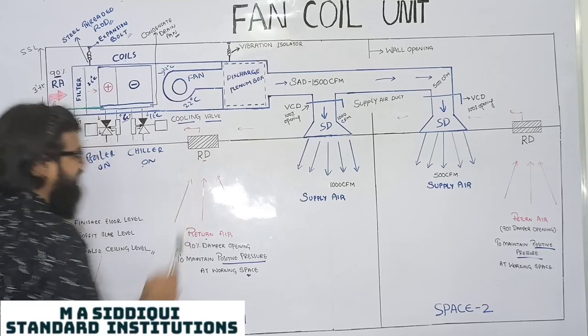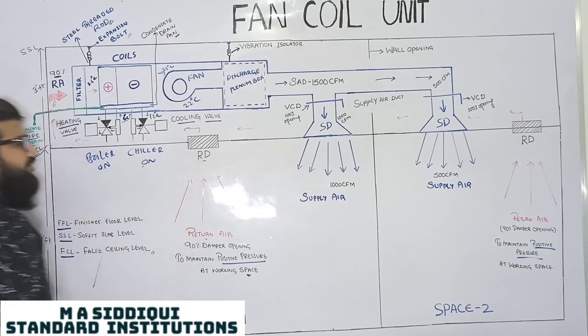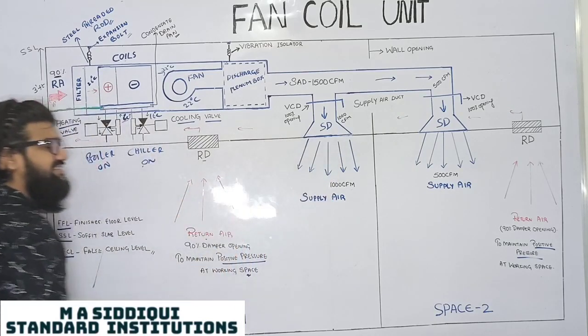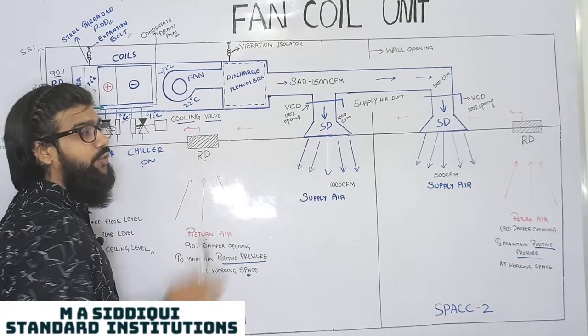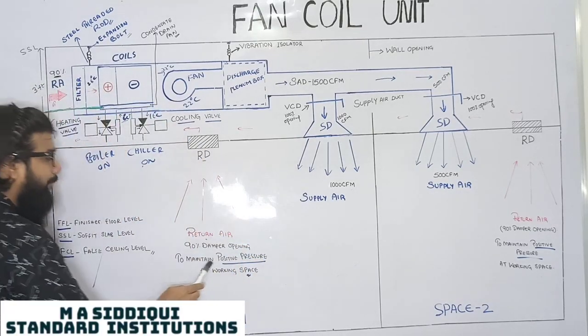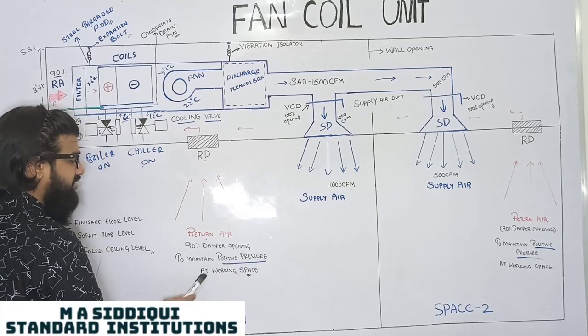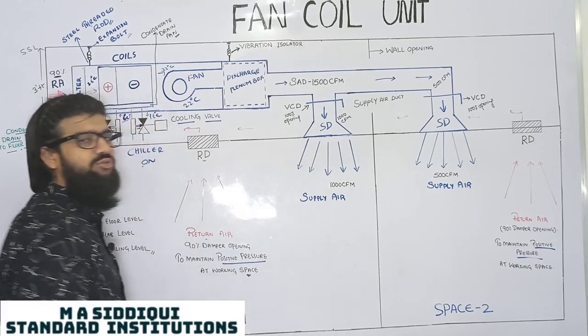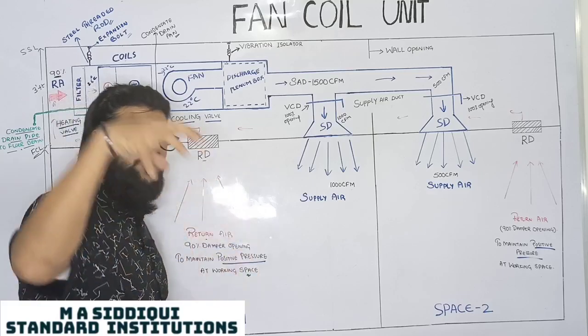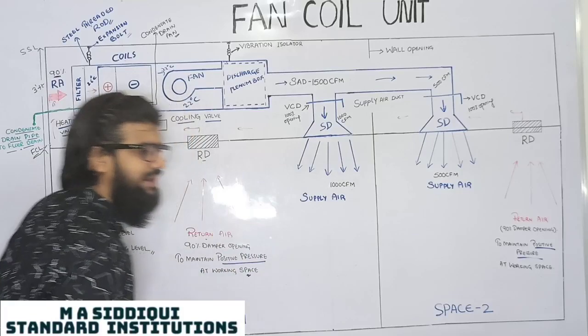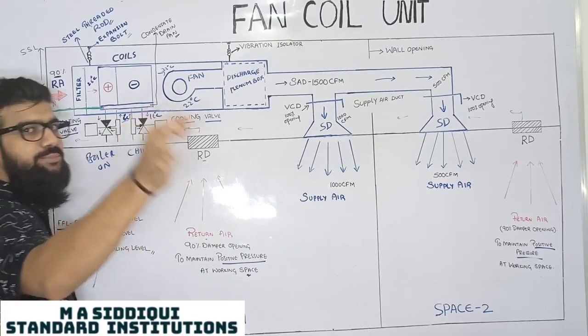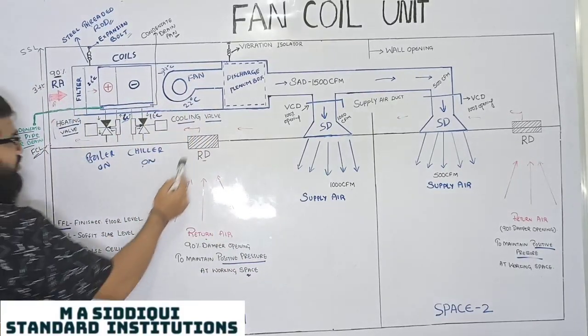While the return air is going from the return diffuser of both spaces, only 90% air will be taken, not 100%. Why? To maintain the positive pressure at the working space. The supply air will be more and the return air will be less compared to supply to maintain positive pressure.